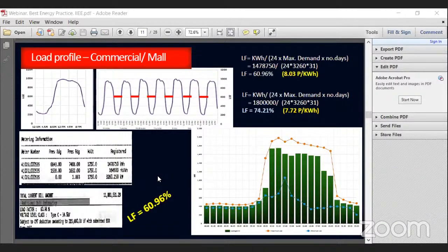Okay, balik tayo sa left side, yung sa billing determinants kanina, pinakita yung energy, reactive, and demand. But for this billing, as you can see, the load factor is 60.96. Mababa yan, pag kinompare mo sa manufacturing, semicon, mataas ang load factor nila, baka 70, 80. So what is the impact of load factor? Yung nasa taas, right side, that is the formula of load factor: kilowatt hour divided by 24 times maximum demand times number of days.